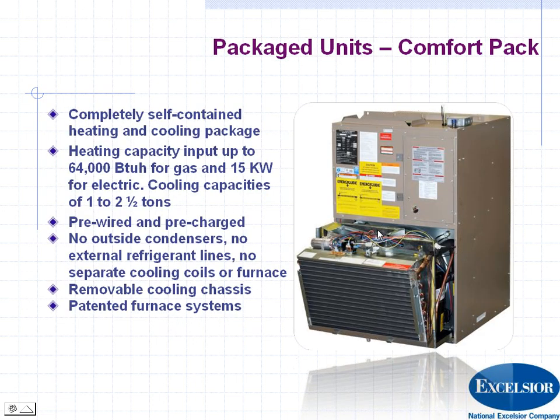A little bit about them. They're completely self-contained heating and cooling package, like we talked about. So they are very easy to spec, very easy to put in, and they are very easy to start up. Don't have a lot of problems. So they're very, very popular in the multi-family new construction market. Again, heating capacity is up to 64,000 BTUs and up to 15 kW for electric heat.